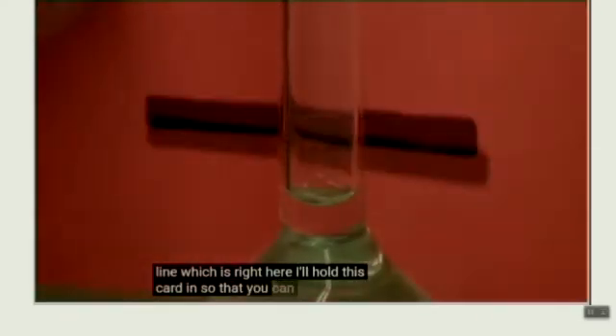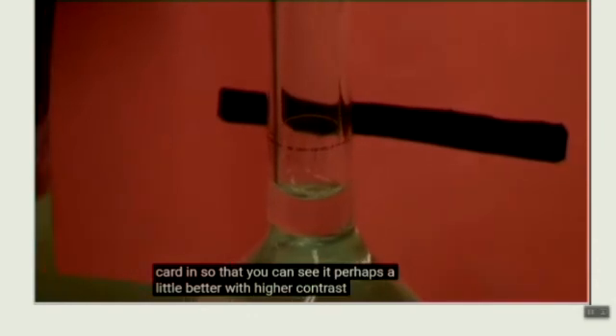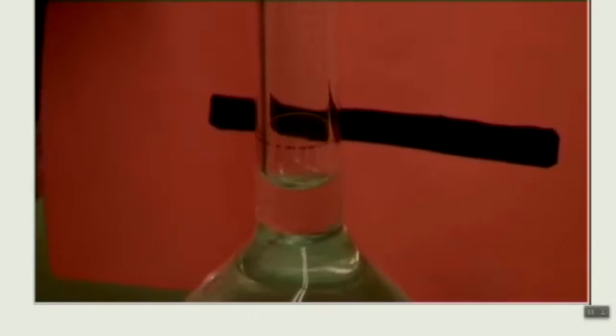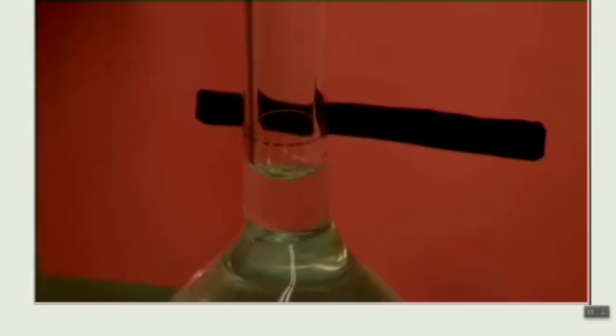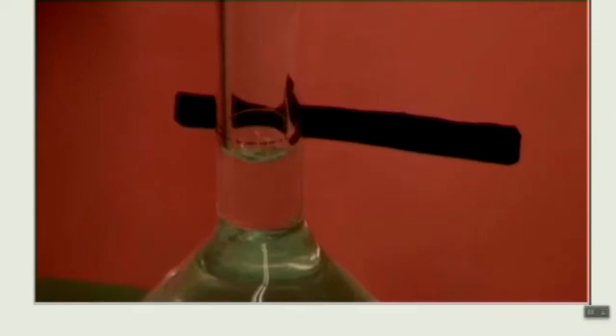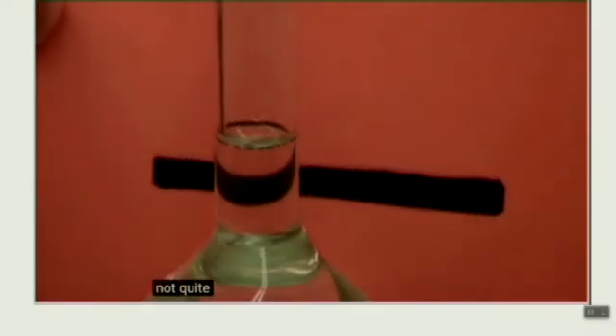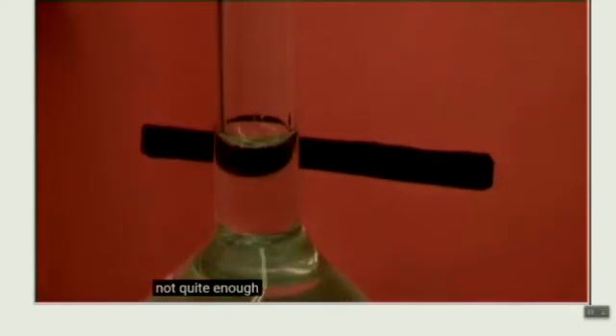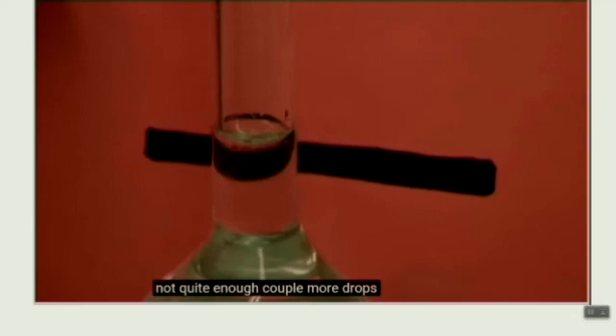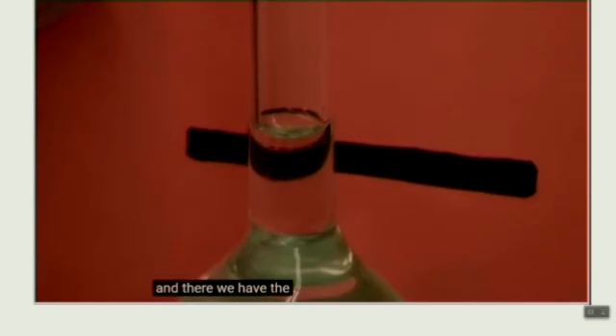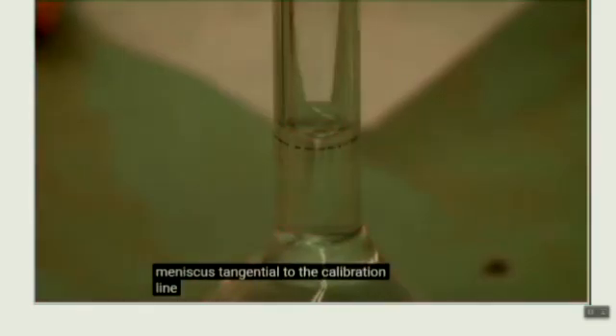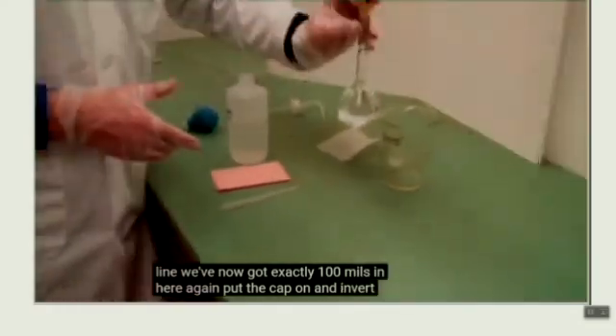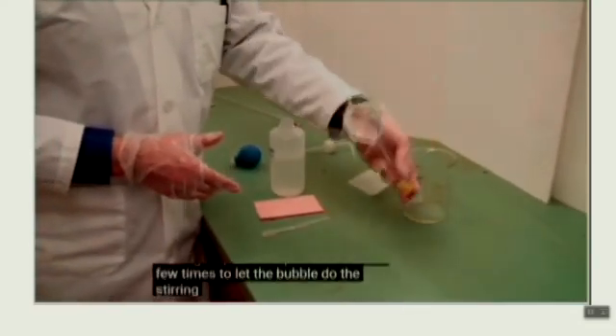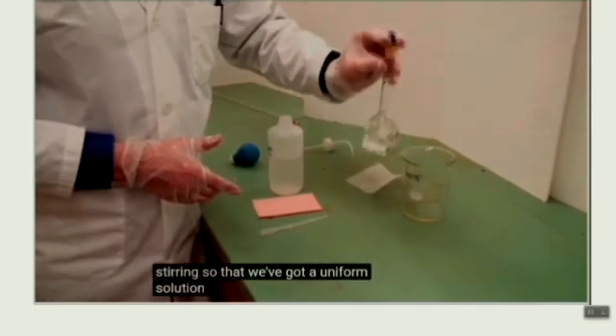I'll hold this card in so that you can see it perhaps a little better with higher contrast. A couple more drops. And there we have the bottom of the meniscus tangential to the calibration line. We've now got exactly 100 mils in here. Again, put the cap on and invert a few times to let the bubble do the stirring so that we've got a uniform solution.